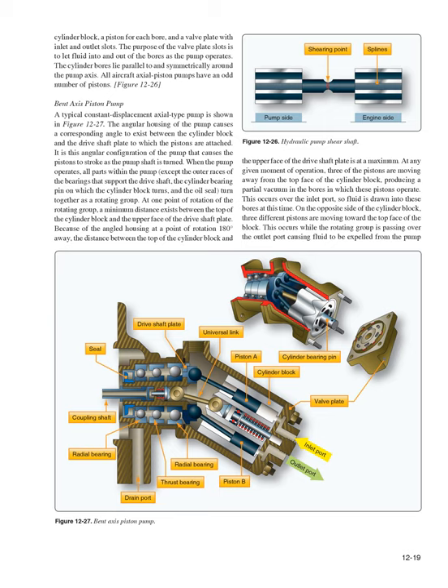Because of the angled housing, at a point of rotation 180 degrees away, the distance between the top of the cylinder block and the upper face of the drive shaft plate is at a maximum. At any given moment of operation, 3 of the pistons are moving away from the top face of the cylinder block, producing a partial vacuum in the bores in which these pistons operate. This occurs over the inlet port, so fluid is drawn into these bores at this time.